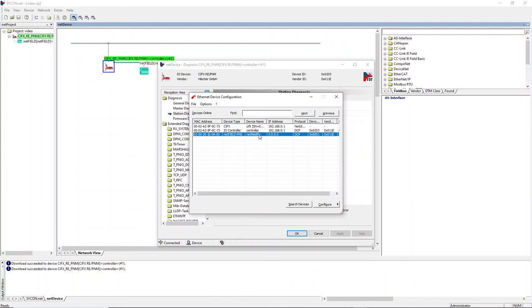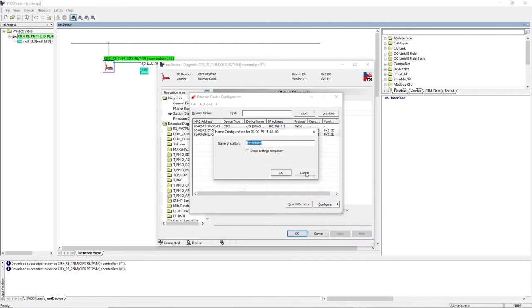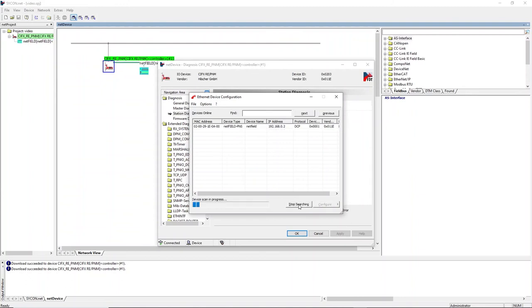Define the needed name of station or device name to the NetField device. This needs to be completely equal to the name defined in the IO controller settings. With another scan, you can see that the IP address will now automatically be set by the IO controller.